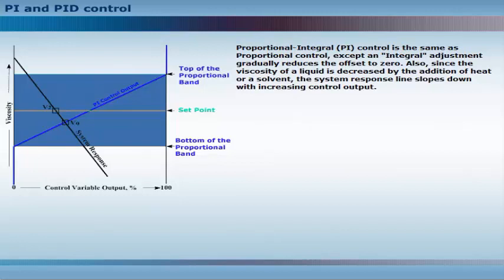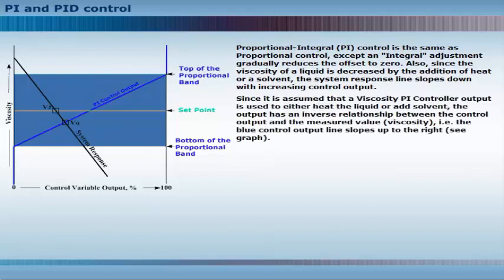Also, since the viscosity of a liquid is decreased by the addition of heat or a solvent, the system response line slopes down with increasing control output. Since it is assumed that a viscosity PI controller output is used to either heat the liquid or add solvent, the output has an inverse relationship between the control output and the measured value, i.e., the blue control output line slopes up to the right.